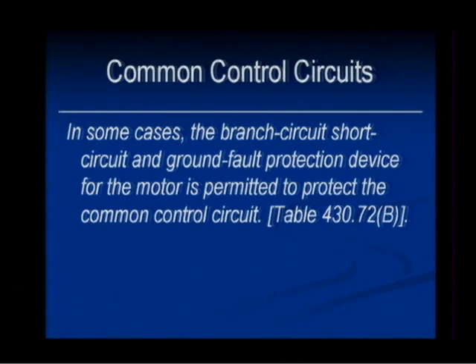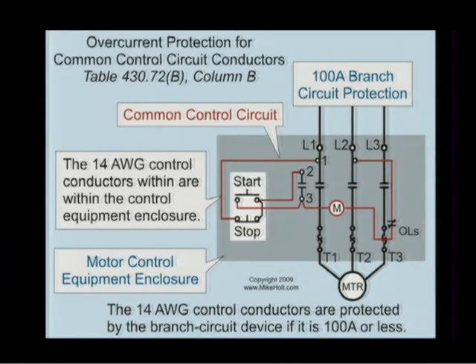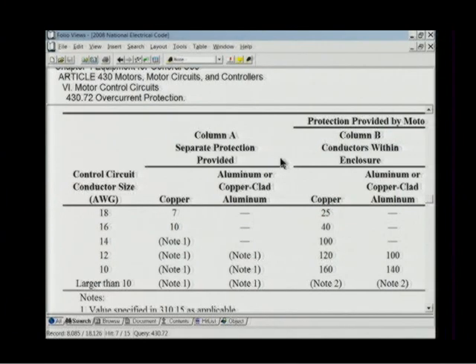In some cases, the branch circuit, short circuit, and ground fault protection device for the motor is permitted to protect the common control circuit. I really like to take a look at this graphic. What we're saying is this: you have a 100-amp breaker and 14-gauge wire. We have no overcurrent protection for these conductors. There are cases where we can use the branch circuit protection to protect these conductors, as long as these conductors have a given size. And that's where 430.72 comes in.